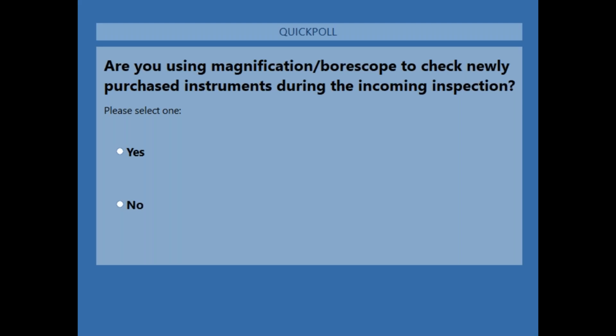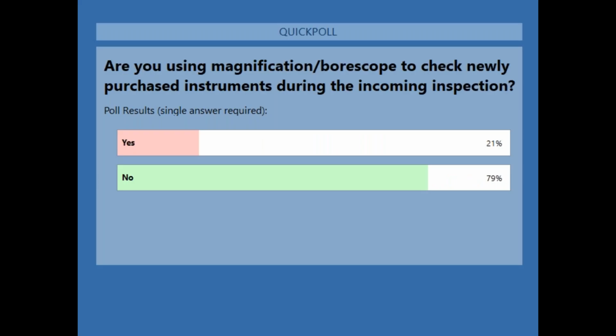No, we'd basically like to know what HTM usually does when doing either a pre-purchase evaluation, trial, or incoming inspection. We really didn't accept that all the instruments or medical devices are in good shape. We didn't take their word for it. So we did a thorough incoming inspection and looked at all the different portions of the devices to make sure that everything is good. We're just trying to find out, do we do the same thing with this? After all, an endoscope is a $30,000, $40,000 piece of equipment that we receive. Do we look inside it when we receive this really expensive medical device?